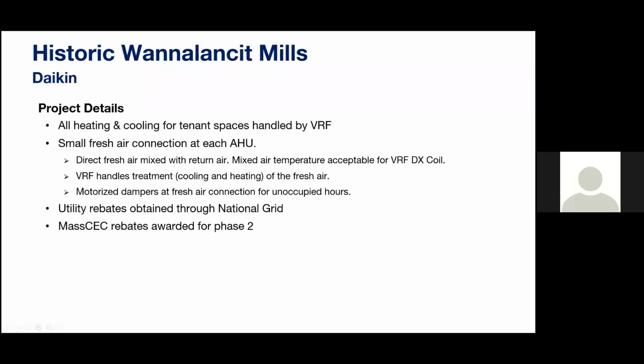Moving on, I don't think I mentioned, but we removed all of the gas heating in the ductwork as well. So all the heating and cooling for the spaces is being handled by the VRF condensing units. To bring in the outdoor air to the space, we're ducting that directly to the back of the air handling units. So when doing this, like Jason mentioned, you need to consider the mixed air temperatures on the coil.